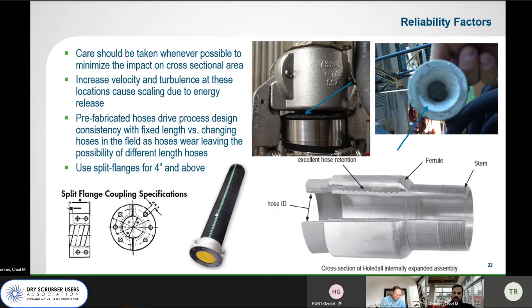Same for the small bore hoses that go to your lances. Typically, these are anywhere from 1.5 to 2 inches. Anywhere you have a constriction in the line cross-sectional area, a lot of times you'll form scale in those areas. So we found a hose fitting that expands from the inside out to maintain the same flow area through the fitting, so you don't have that constriction and possible scale formation site. So all of our smaller bore hoses, we use these internal expansion stems. And then the large bore piping, like 4-inch, 6-inch, we use clamp-on flanges that are easily taken apart and serviced for maintenance if needed.